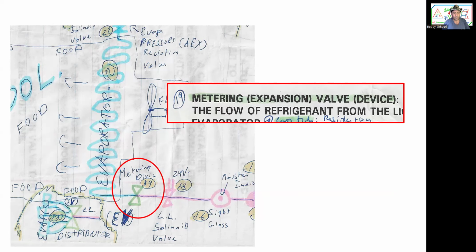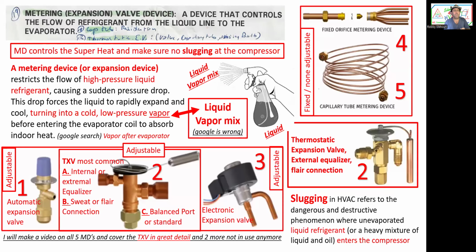As we know by now, the metering device regulates the flow. The metering device controls the flow of refrigerant from the liquid line to the evaporator, right? The metering device controls the superheat and makes sure there's no slugging at the compressor. I'll cover slugging more later, when we do the compressor, the expansion valve, and the evaporator. A metering device or expansion device restricts the flow of high pressure liquid refrigerant, causing a sudden pressure drop. This drop forces the liquid to rapidly expand and cool, turning into a cold, low pressure vapor liquid mix before entering the evaporator coil, absorbing indoor heat.